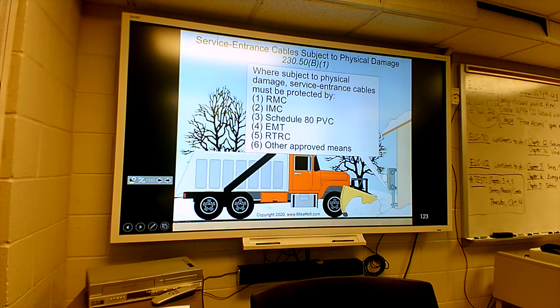So RMC is rigid metal conduit. That's the really thick wall stuff. IMC is intermediate. That's a little bit thinner than rigid. Schedule 80 PVC. Schedule 80 is the thickest PVC, to where Schedule 40 is thin wall PVC. So you can't use Schedule 40, but the 80 you can. And then EMT, that's the thin wall electrical metallic tubing. It's this conduit here that you had.